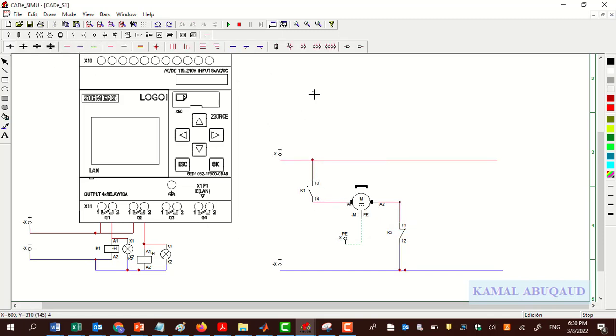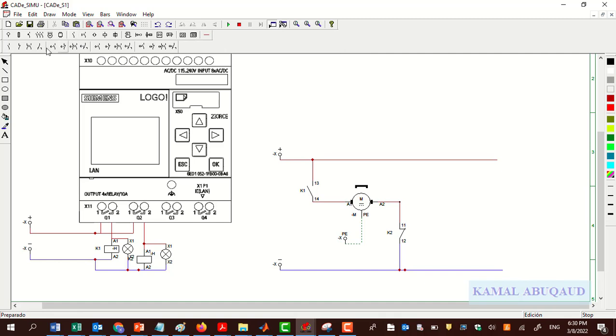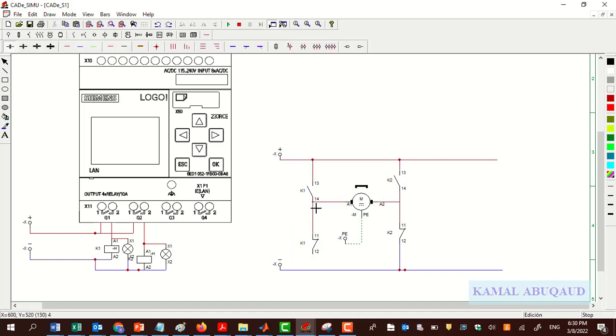The circuit that runs the motor in the reverse direction consists of a normally open contact controlled by relay two and a normally closed contact controlled by relay one. Having a normally closed contact in each path provides a physical interlock, which means the motor can run only in one direction at any time.